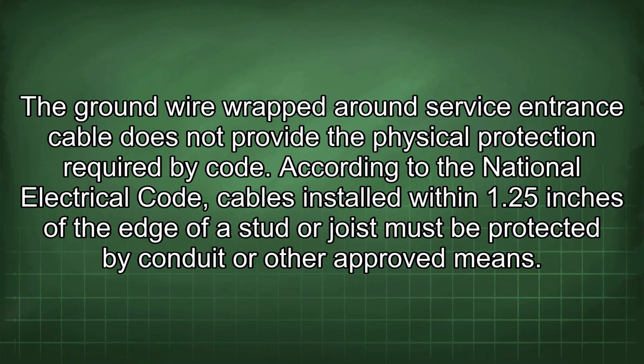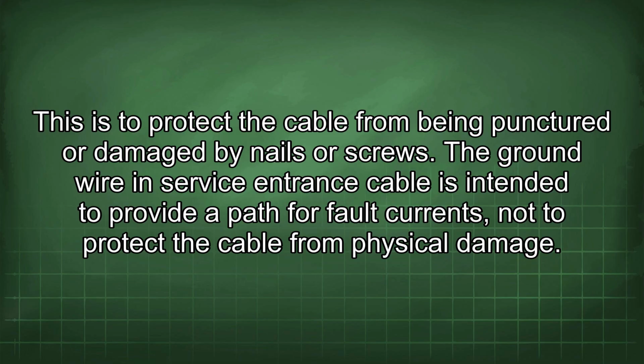The ground wire wrapped around service entrance cable does not provide the physical protection required by code. According to the National Electrical Code, cables installed within 1.25 inches of the edge of a stud or joist must be protected by conduit or other approved means. This is to protect the cable from being punctured or damaged by nails or screws.